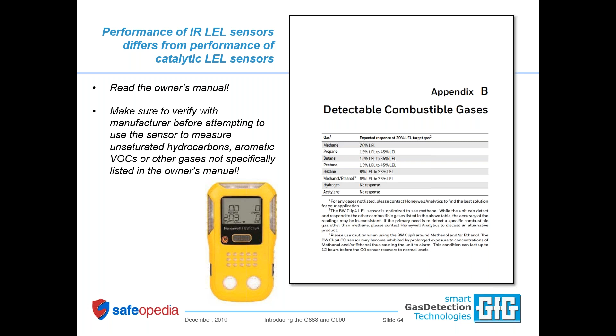But if you have nothing but methane, God bless. It's a great product and a great sensor. Now, where do you find pure methane? Not that often. Is natural gas pure methane? No. Natural gas has a variable concentration of ethane and propane. That means that with regards to natural gas, you're immediately in the area that you're warned against with the fine print in the manual. Your readings are likely to be inaccurate. If you care about taking action at 10% LEL, well, good luck to you.